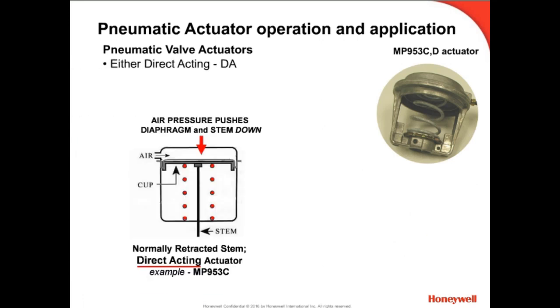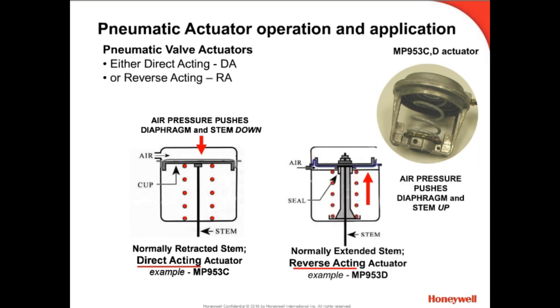We will control either valve type with either a direct acting or reverse acting actuator, which will then give us our final control configuration. Air pressure on the diaphragm of the direct acting actuator will push the actuator stem down, compressing the spring and extending the stem. As air pressure is removed, the spring will retract the stem. Thus, the normal position is stem retracted, listed as a normally retracted stem actuator or direct acting. Conversely, air pressure on the diaphragm of the reverse acting actuator will push the actuator stem up, compressing the spring while retracting the stem. As air pressure is removed, the spring will extend the stem back out. Thus, the normal position is stem extended, listed as a normally extended stem actuator or reverse acting. Note there is no valve in this diagram, so there is no normally open or normally closed discussion possible at this point.